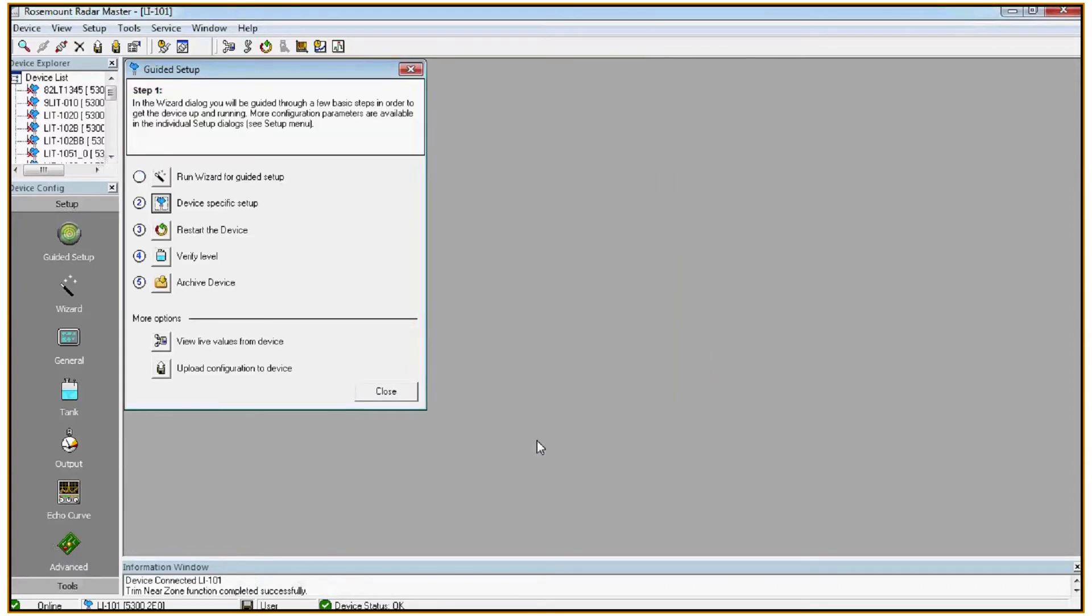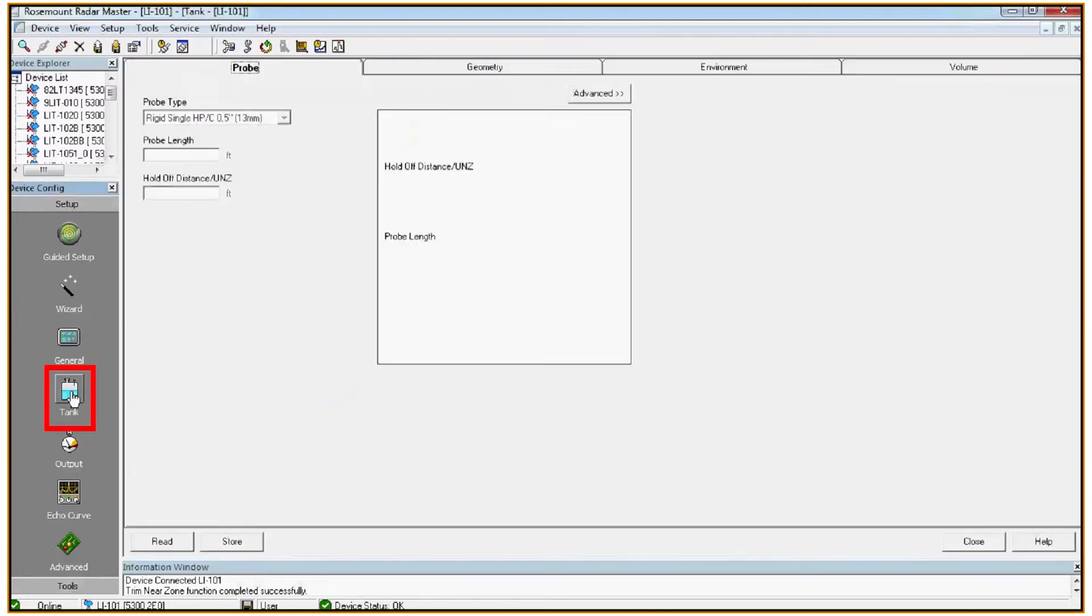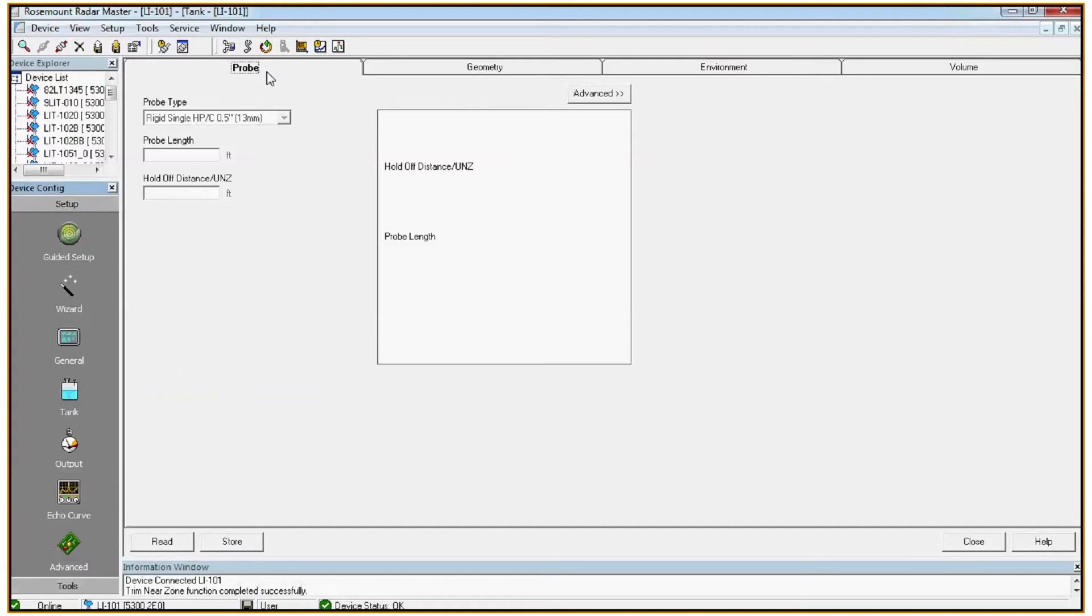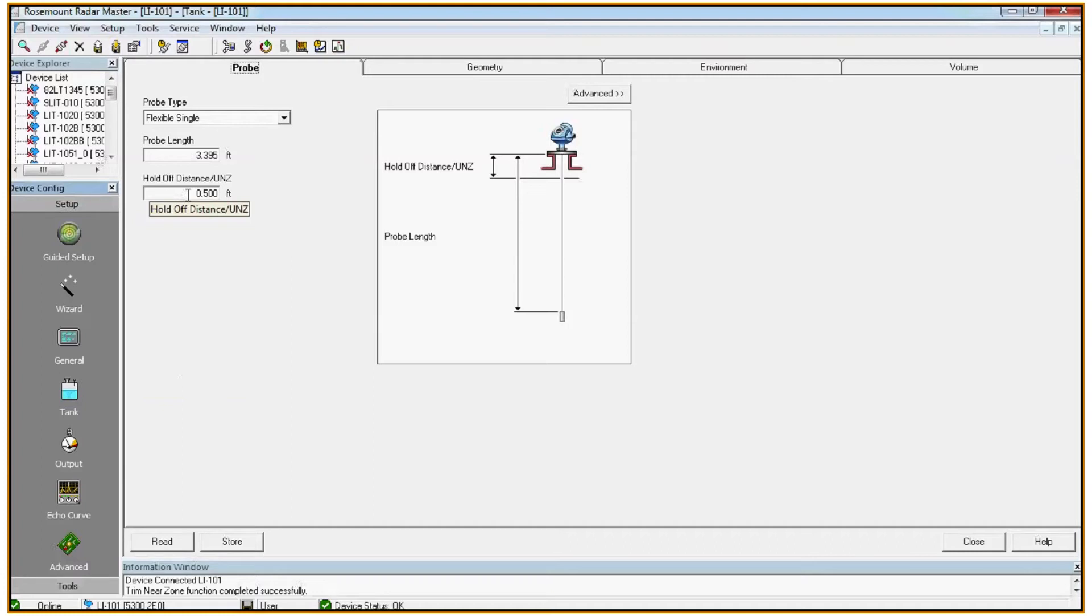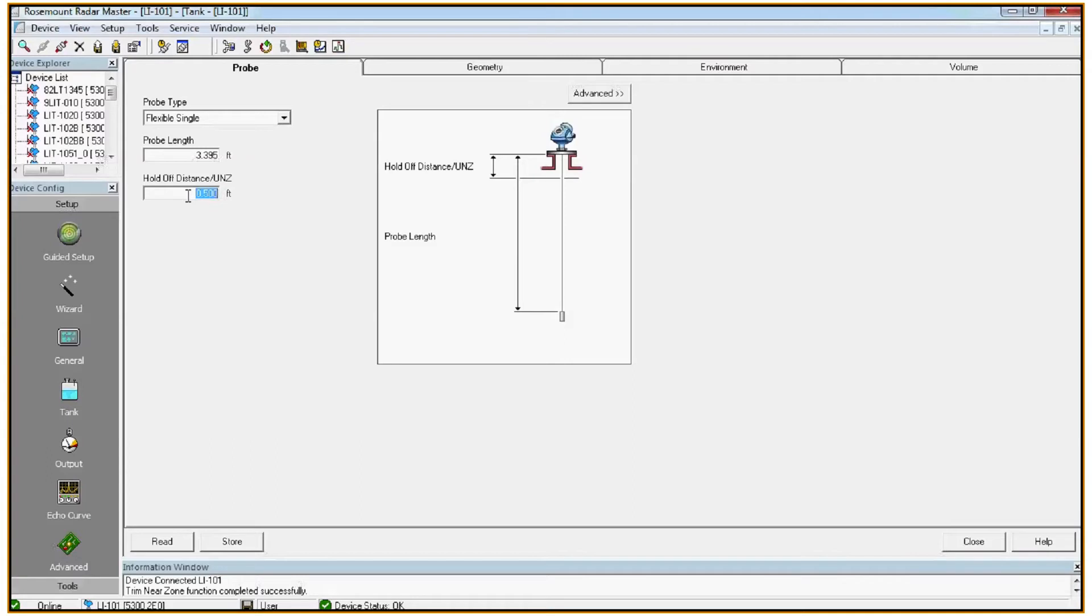Next we're going to go into the tank configuration. We'll start at the probe tab and we want to make sure that we configure our hold off distance. The hold off distance is the area at the top of the tank that we know we'll never get product in, so we want to make sure that we ignore it completely. In this case I know that the nozzle was about half a foot long, so we'll make sure we set the hold off distance to half a foot. It's important to note that you can't actually measure in the first half a foot from the flange anyway. So it's always a good idea to have an upper nozzle or hold off distance of at least half a foot.